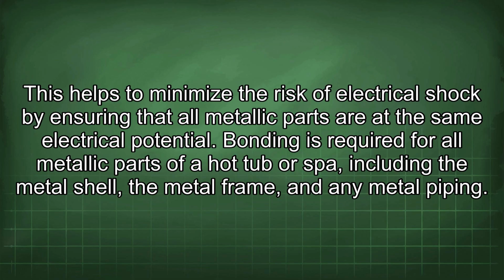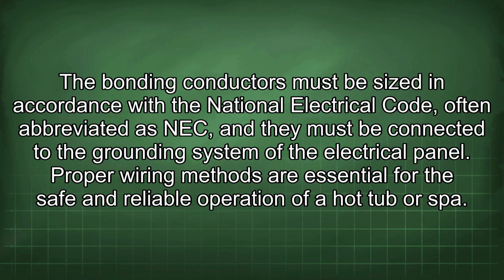Bonding is required for all metallic parts of a hot tub or spa, including the metal shell, the metal frame, and any metal piping. The bonding conductors must be sized in accordance with the National Electrical Code, often abbreviated as NEC, and they must be connected to the grounding system of the electrical panel. Proper wiring methods are essential for the safe and reliable operation of a hot tub or spa.